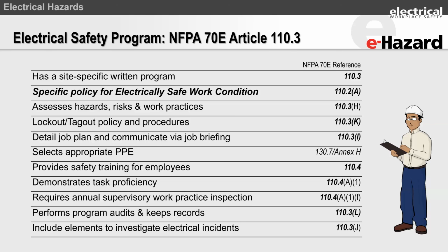You've got to say, here's the clothing that we're using. Take the red bag when you're working on equipment that has the orange label that says 8 calories per square centimeter, or category 2, or level 2. And take the orange bag, which has the flash suit, if it says level 4 or 40 calories per square centimeter. That's the kind of detail that you will not find in the NFPA 70E.